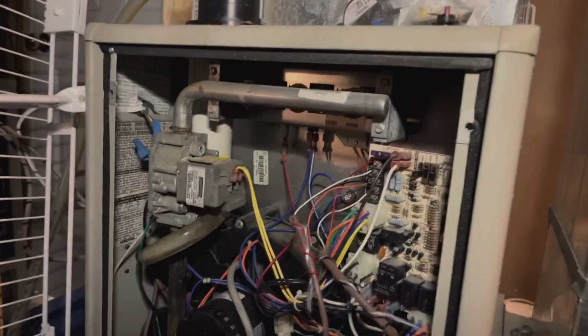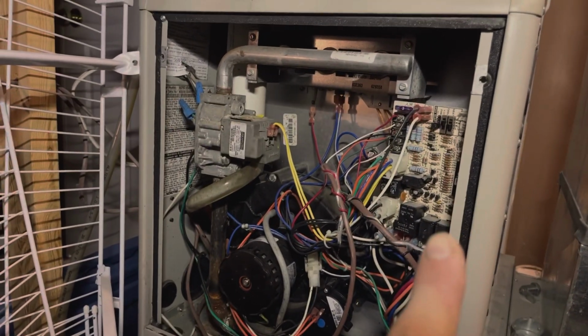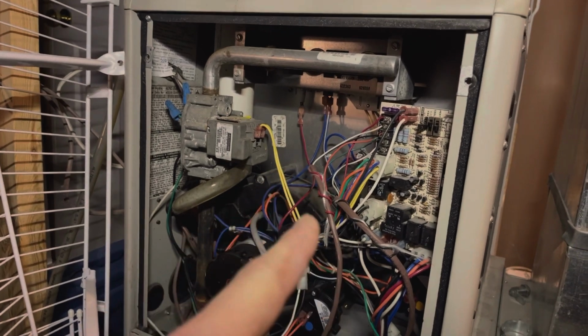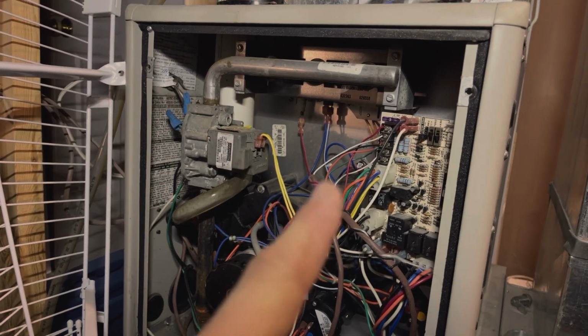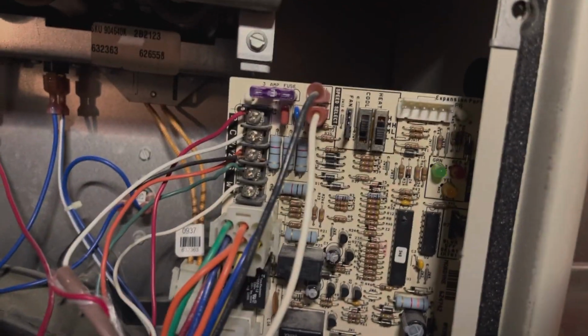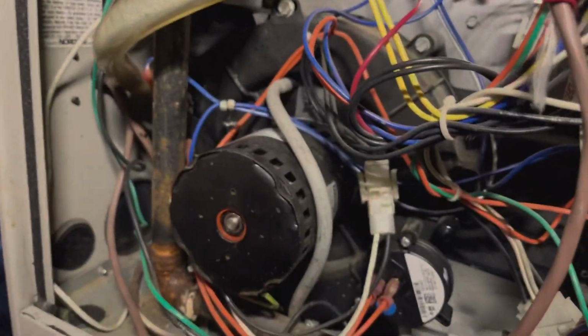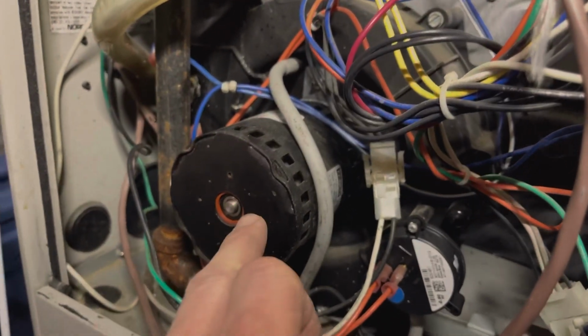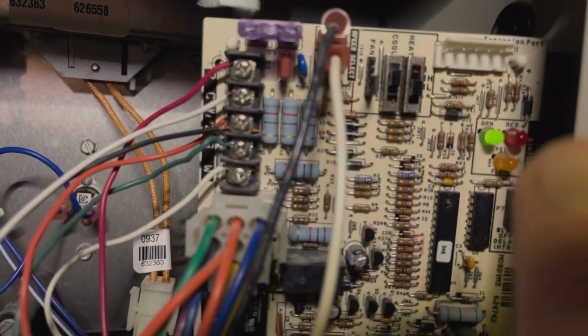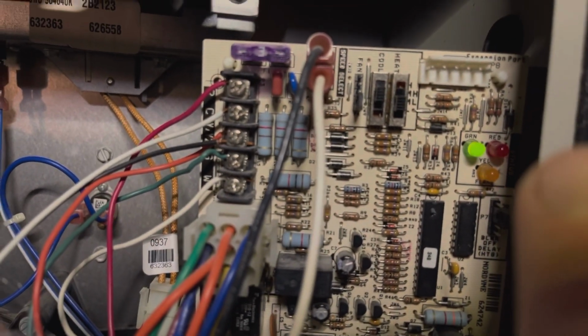Okay, so now with that unplugged, I'm going to turn on the switch, and the thermostat is turned up, so it's going to call for heat. I'm going to run back over here, and this should have a flashing fault indicator. Okay, I switched it on. You hear it click. It calls for heat, and look at that. The inducer motor started, so you know the inducer motor's good in this furnace, but we got that green flashing light, red off, yellow off. So what does that mean?